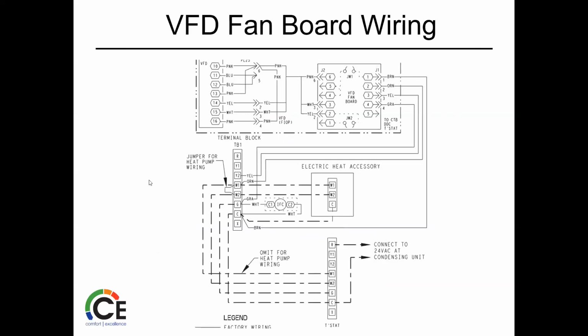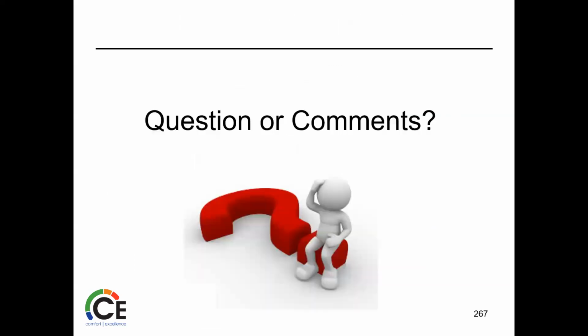And then, of course, here's just a wiring breakdown of where that goes. It comes from the unit, hits here, and then it's distributed out through the VFD fan board, and then hits the actual VFD control. So, VFDs, we know that they fail, right? We know it's a pain in the neck.